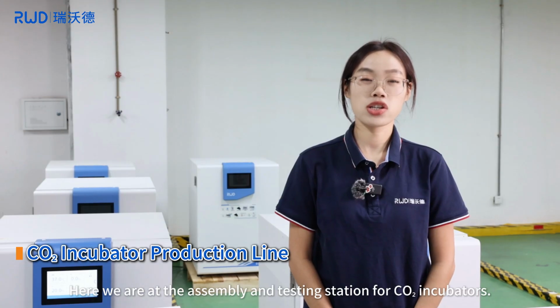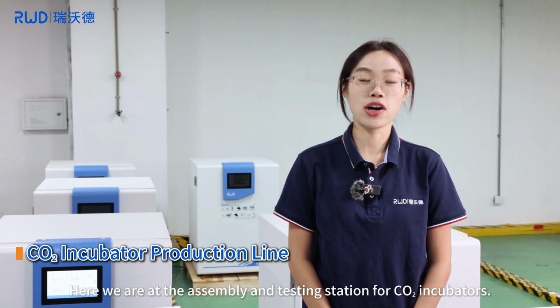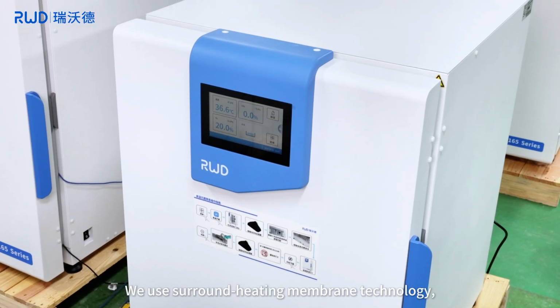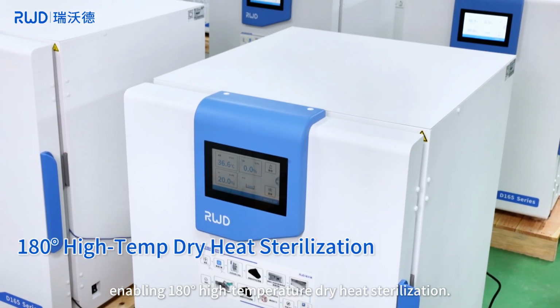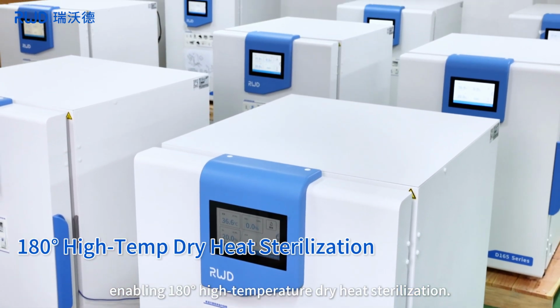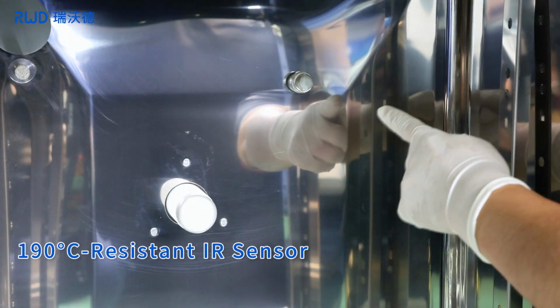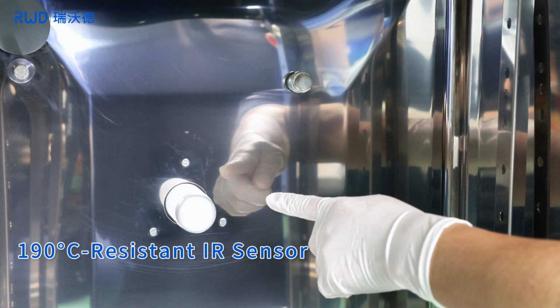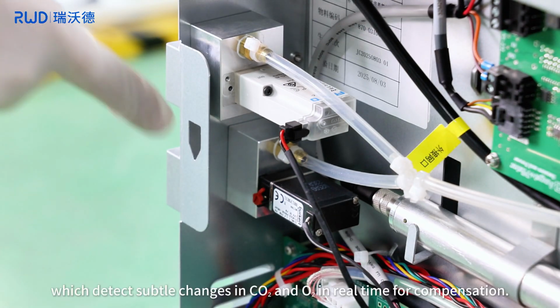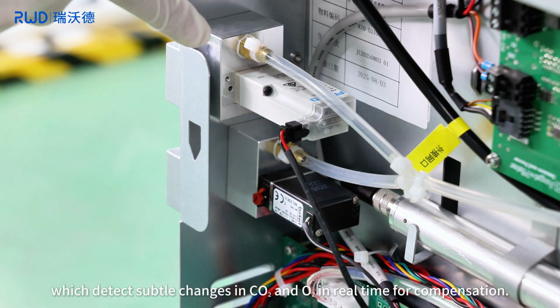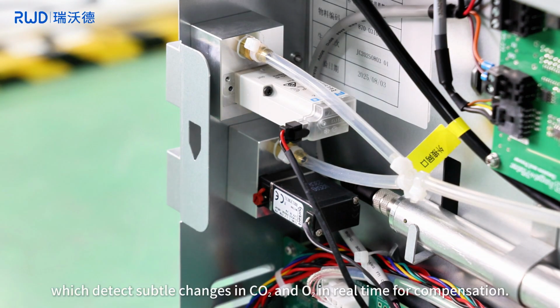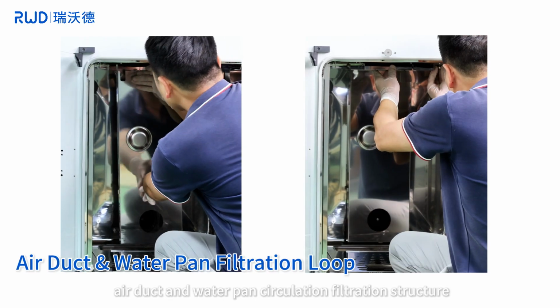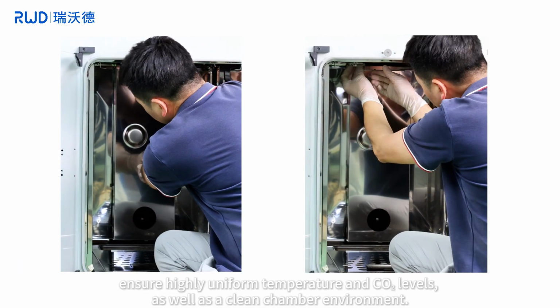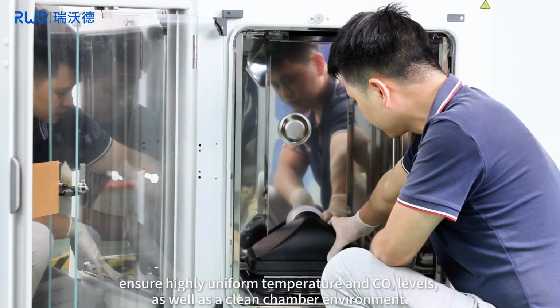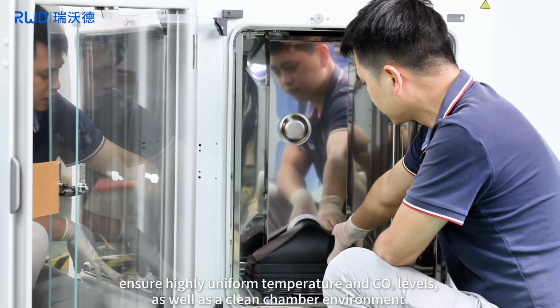Here we are at the assembly and testing station for CO2 incubators. We use surround heating membrane technology, enabling 180 degrees high temperature dry heat sterilization. It is equipped with an IR sensor resistant to 190 degrees Celsius and a high-precision solenoid valve, which detects subtle changes in carbon dioxide and oxygen in real time for compensation. The internally designed air duct and water pan circulation filtration structure ensure highly uniform temperature and CO2 levels, as well as a clean chamber environment.